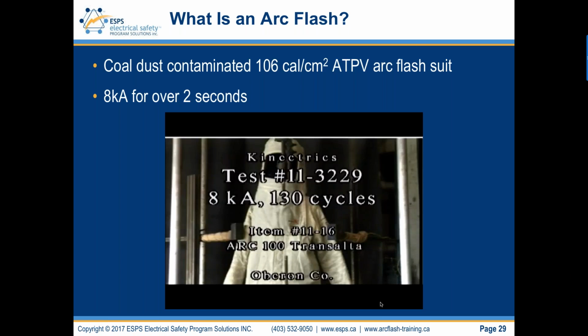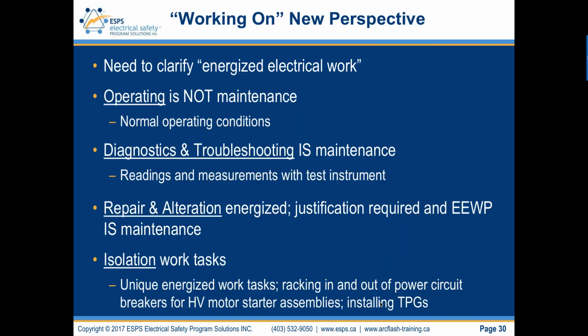The after flame was not significant. Therefore, it's only a sample of one, though. So one questions whether the coal dust flashed off and the PPE performed. The other issue here is because of the fault current and the fault clearing time, we don't see a lot of blast pressure released from this arcing fault. And again, that discussion needs to continue to occur.